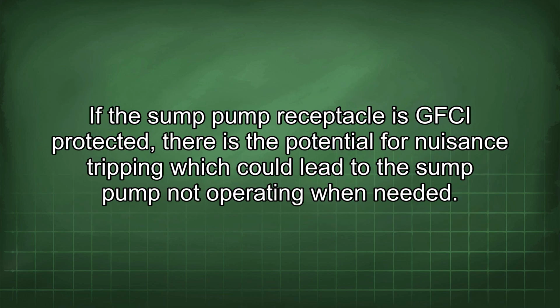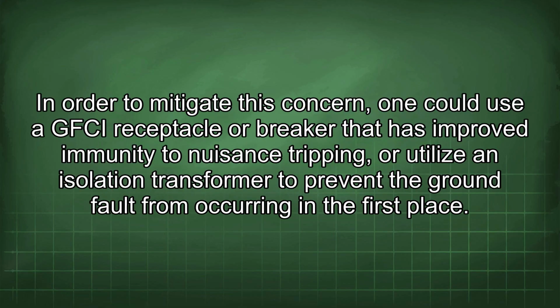If the sump pump receptacle is GFCI protected, there is the potential for nuisance tripping, which could lead to the sump pump not operating when needed. In order to mitigate this concern, one could use a GFCI receptacle or breaker that has improved immunity to nuisance tripping, or utilize an isolation transformer to prevent the ground fault from occurring in the first place.